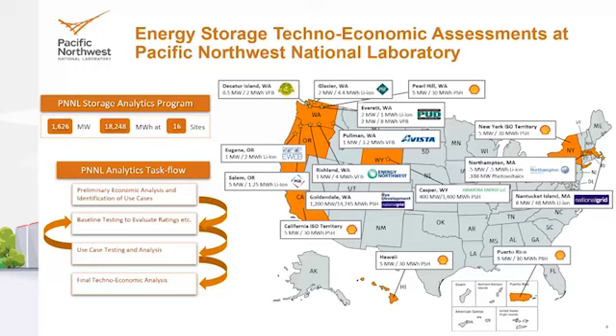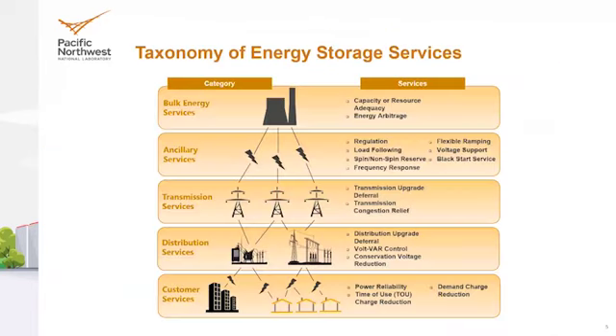We're evaluating 16 sites, 1.6 gigawatts, 18.2 gigawatt hours of storage. When I say gigawatts and gigawatt hours, I mean that at any given point in time, these energy storage systems could collectively provide 1.6 gigawatts of power to the grid, and the 18.2 gigawatt hours is how much stored energy there is. So if I'm evaluating a 1 megawatt, 4 megawatt hour energy storage system, that means if it functions properly, it could provide 1 megawatt of power for 4 hours before being depleted.